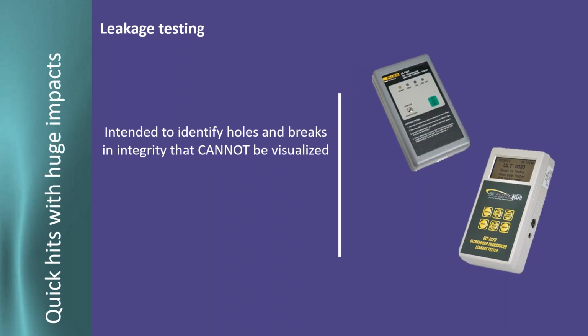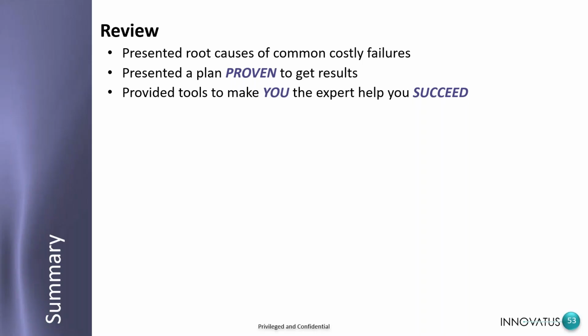And then leakage testing. There are multiple different leakage tests out there. Some come from third parties, some come from the OEMs, some will quantify, like this particular one from BC Biomedical. It will quantify the leakage. Some are more passive. This one particular one from Fluke just gives you a pass-fail, red light, green light. And I kind of like the red light, green light. They're preset to certain parameters, certain leakage settings. If that threshold is breached, the little light turns red. And so you're not trying to explain different levels to people who may not be technical in SPD or cardiology.